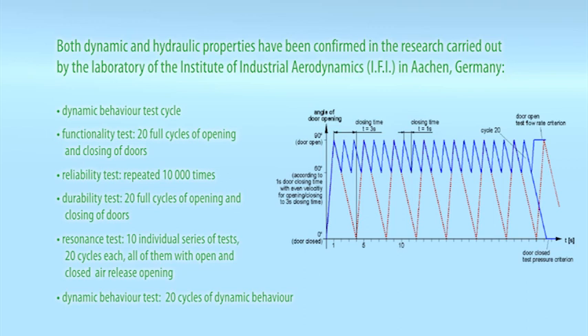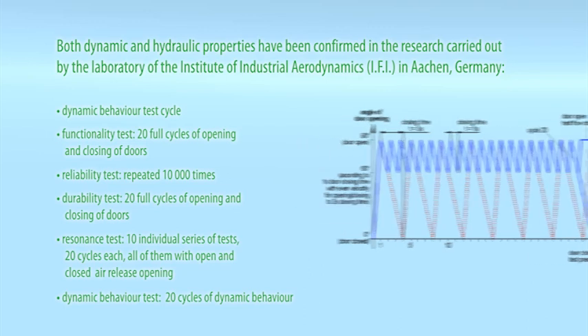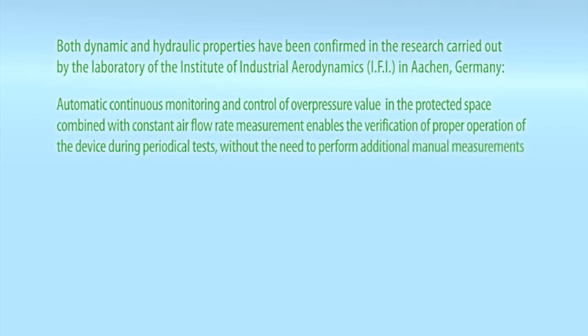Automatic continuous monitoring and control of overpressure value in the protected space, combined with constant airflow rate measurement, enables the verification of proper operation of the device during periodical tests without the need to perform additional manual measurements. Simple method of documentation of periodical tests in the form of automatically printed test reports. Antifrost system.